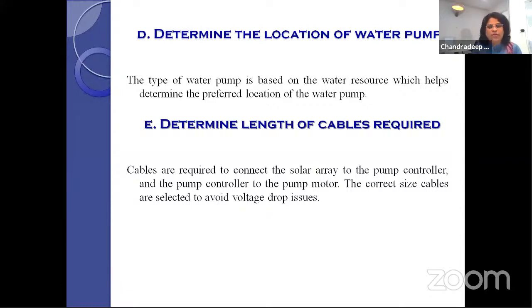So solar array to the pump controller, and pump controller to the pump motor. The correct size cables are selected to avoid voltage drops. Selection of cables depends on their ampere rating, which is a different calculation we're not including here since it needs a separate class. Just remember correct size cables are required, designed as per the voltage drop and current flow in the cables.